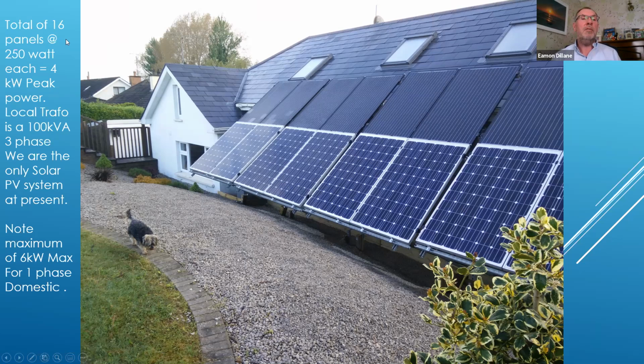Just very quickly, notes down the left here, I've got 16 250 watt panels giving me a 4 kilowatt peak. That's the DC peak output. Now I have a local transformer, which is literally, I'm on the edge of the town. So it's actually a 100 kVA pole mounted 3-phase transformer, literally behind my garden. And we're the only solar panel on that at present.